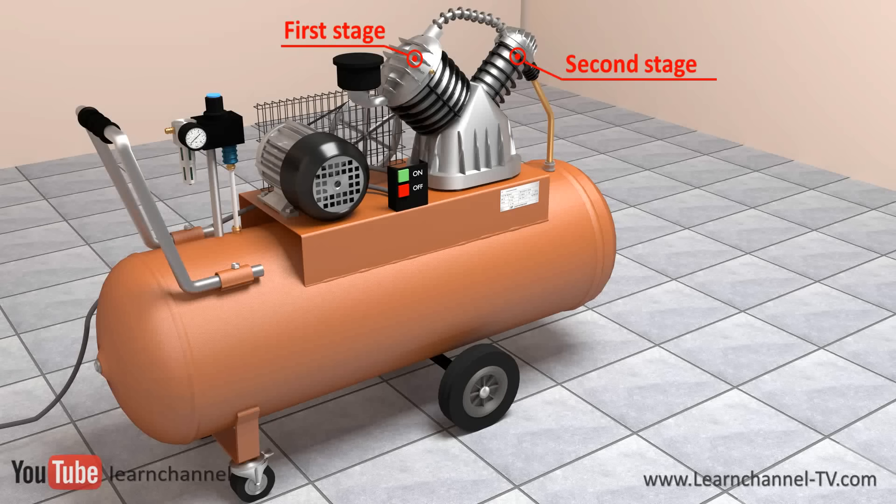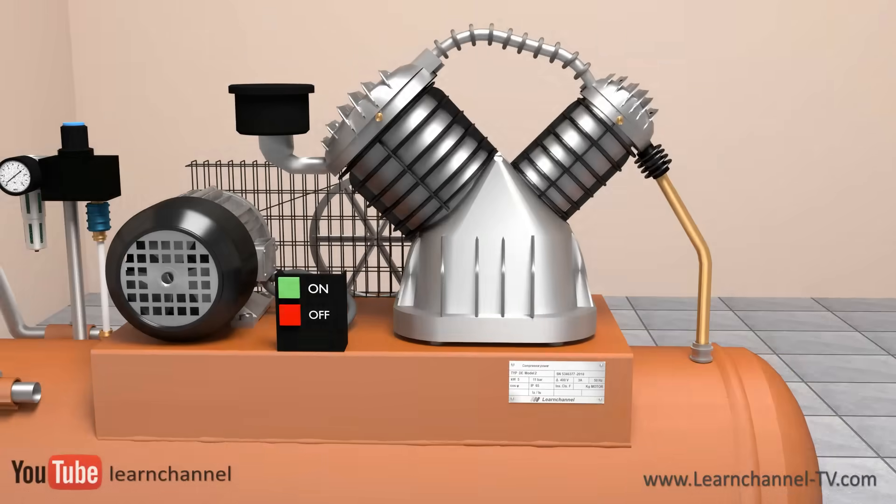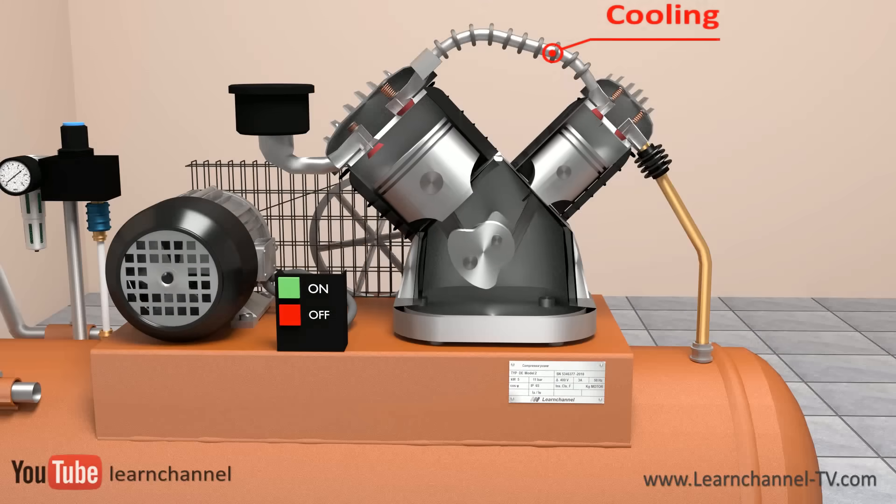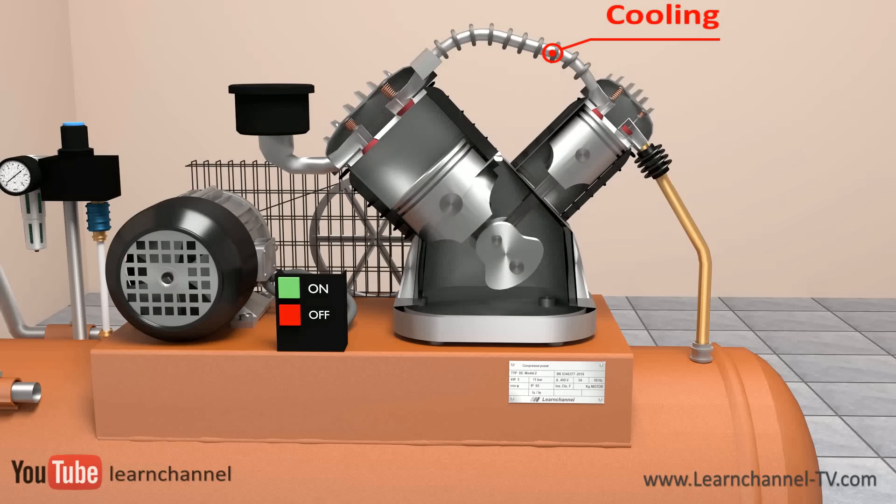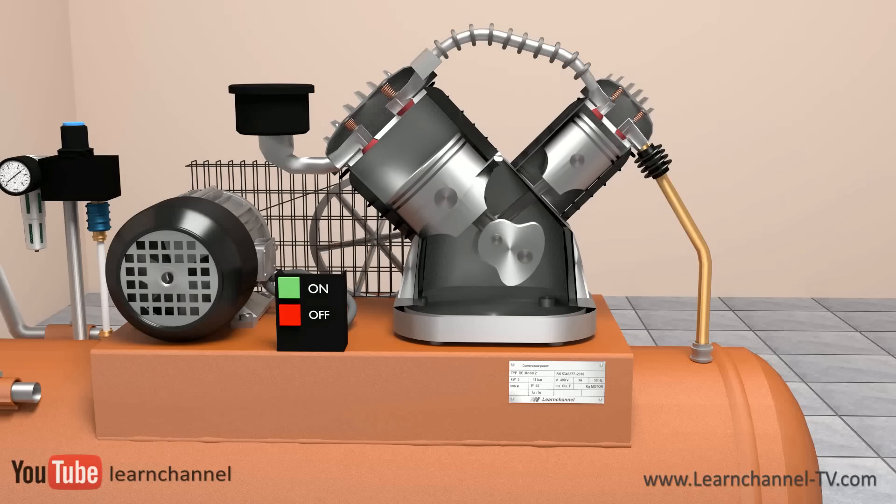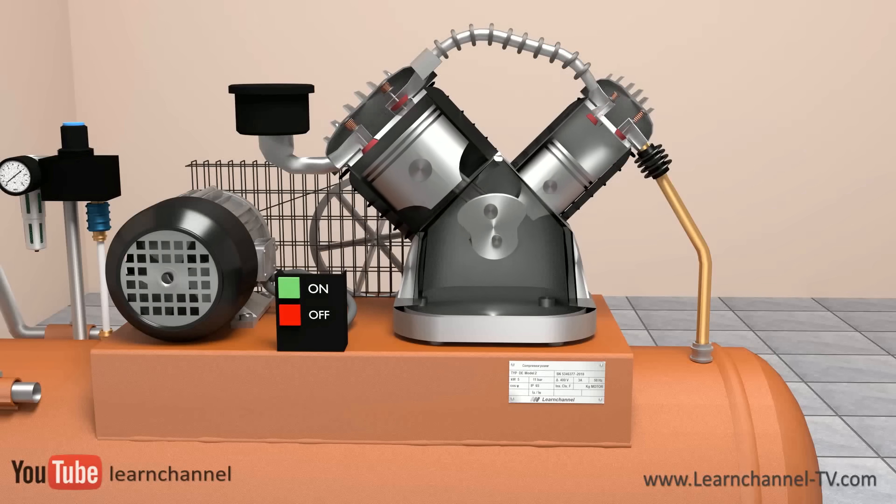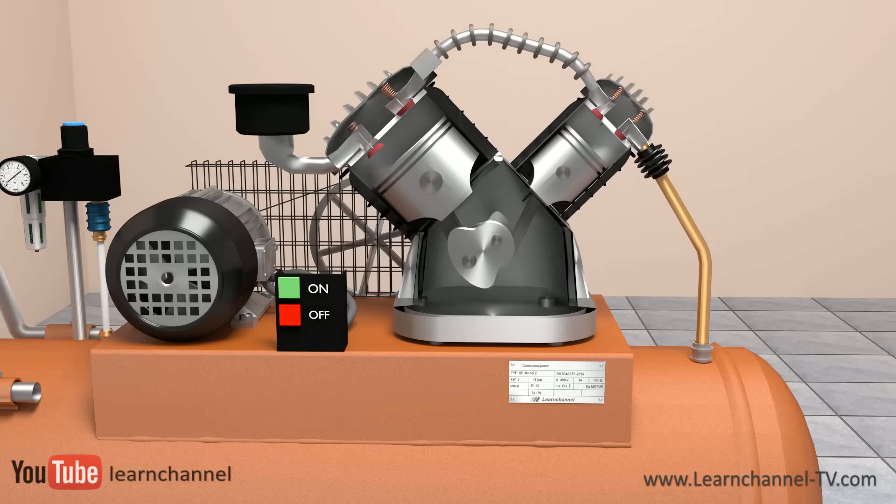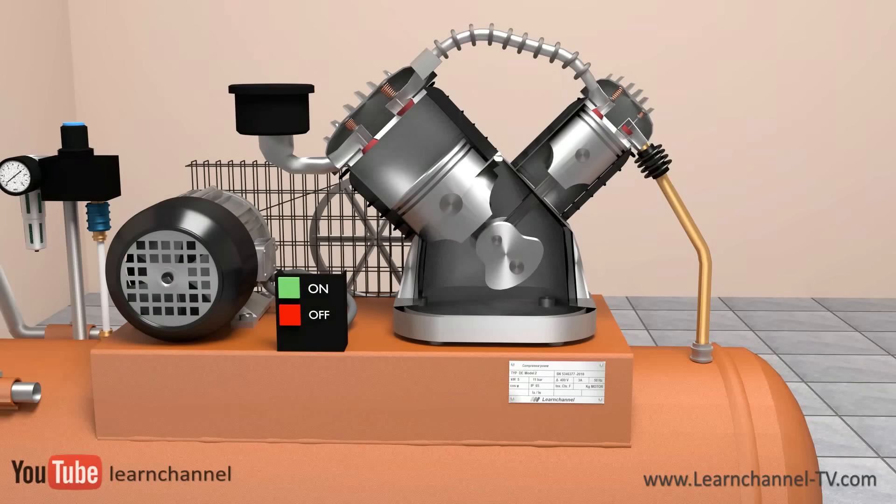To achieve higher pressures, you would use a multi-step compressor. Here, a two-stage compressor is shown. The large piston builds the first stage. The air leaving the first stage can now be cooled before it enters into the second stage. With a two-stage compressor, you achieve pressures over 20 bars, or 290 psi.